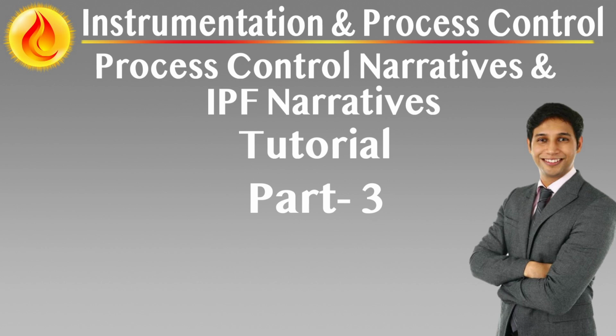Manual reset, overrides, and bypass logic. Many IPFs require deliberate operator intervention after activation. The following must be specified: whether the IPF requires a manual reset and under what conditions it is permitted, whether operational or maintenance overrides are allowed, and how they are activated, displayed, and time-limited. The presence and behavior of startup overrides, manual shutdown capability if required for functional safety. SIL-rated IPFs must comply with override handling rules, including the use of maintenance override switches, MOS, for SIL 2 functions.